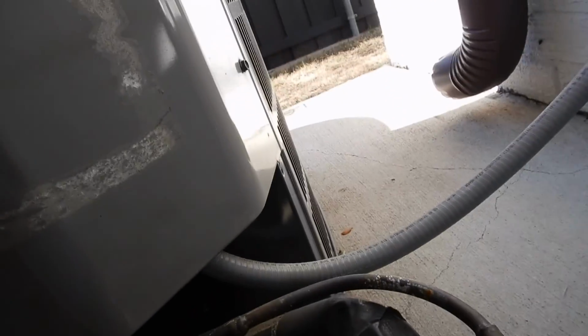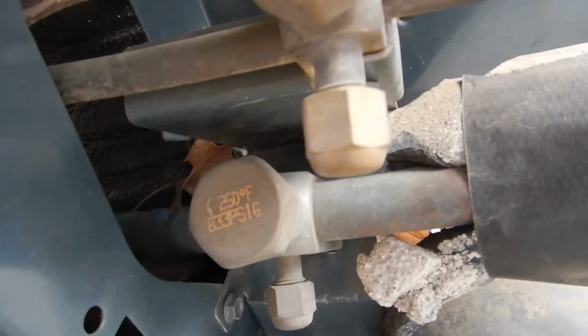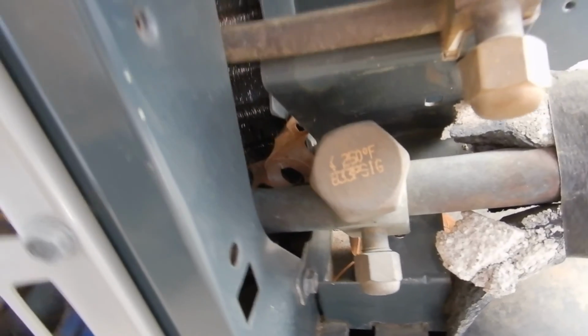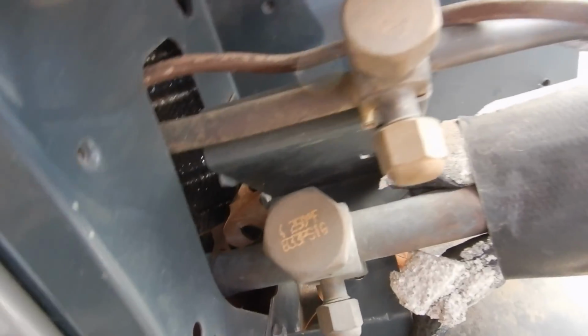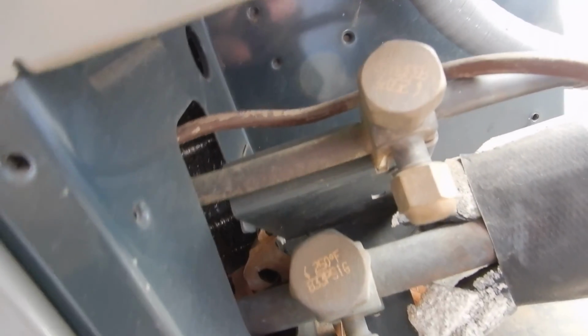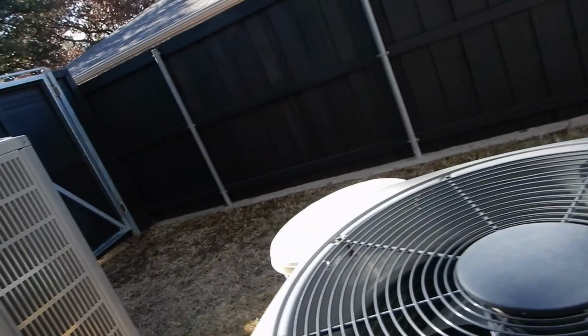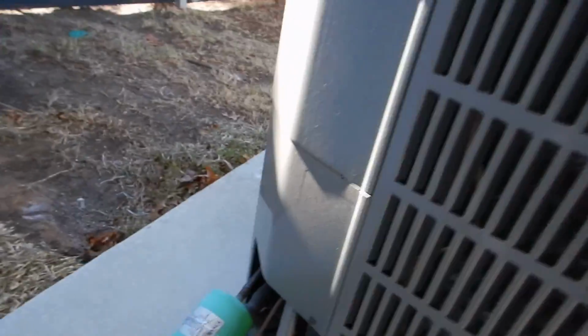These were installed in 2017. See these caps right there for the refrigerant service line port, the Schrader valve caps? Look that up in the dictionary. The refrigerant line service valve port caps should be anti-theft Schrader valve caps. And they're not. Again, the wrong kind of foam and the wrong kind of valve caps.